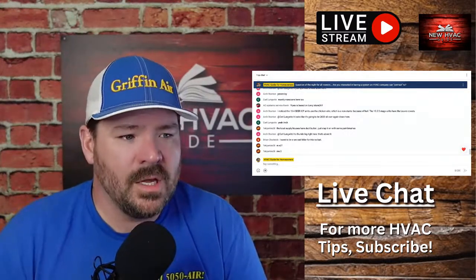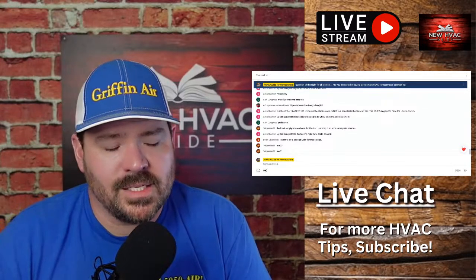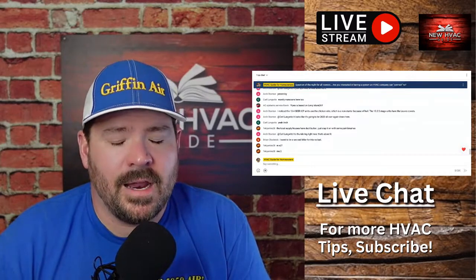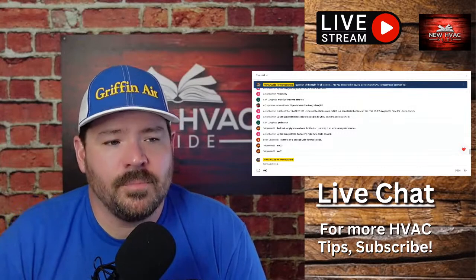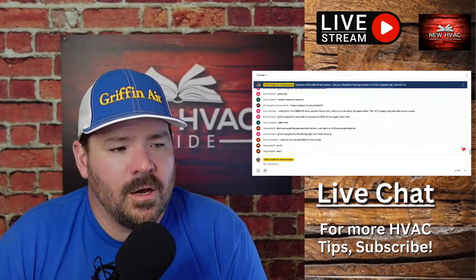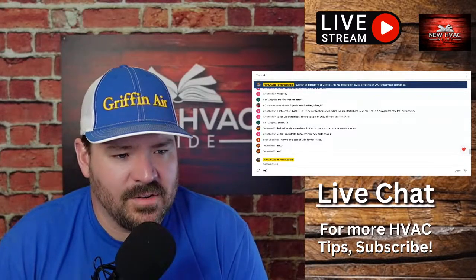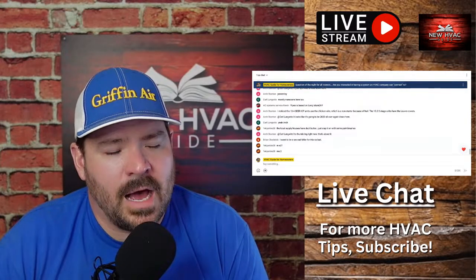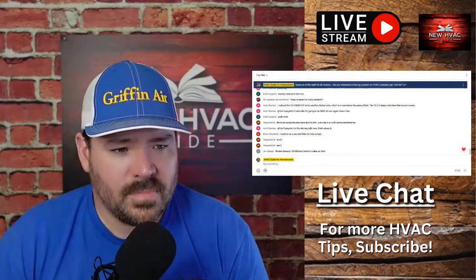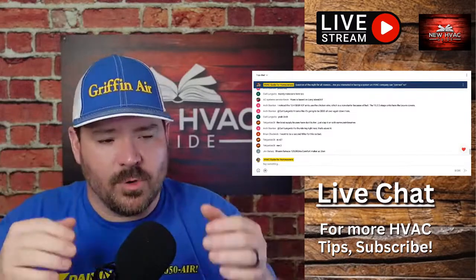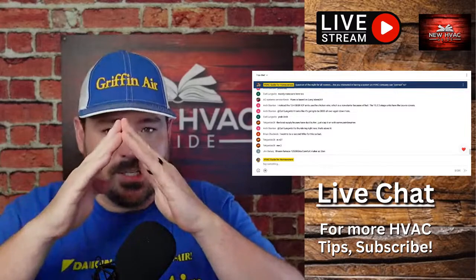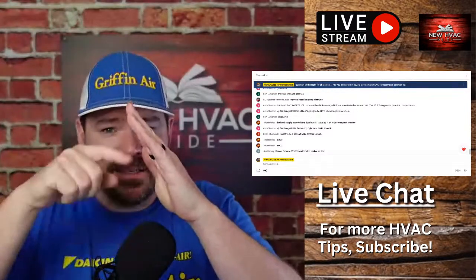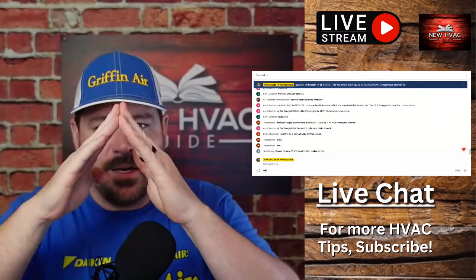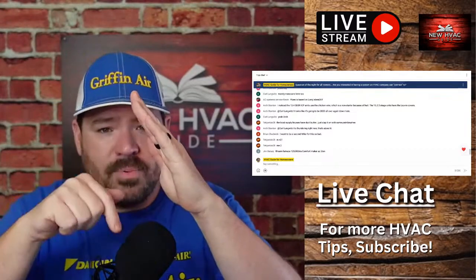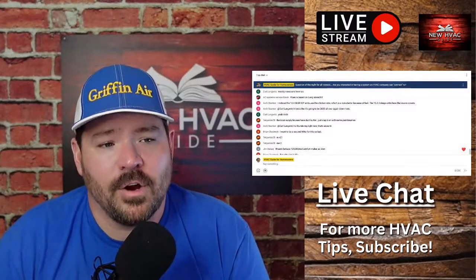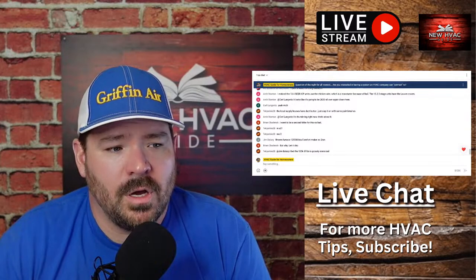Yes, there is. There's literally thermostats that you can turn on the extended fan runtime. The one I know off the top of my head that has it is the Honeywell 8000, because we've turned it on for dual fuel systems multiple times. But I'm sure it's not the only one, there's several out there with extended fan runtime. The other thing I would look at, Dave, is having your AC refrigerant checked. I don't know the configuration of your system, but I've seen A coils that will literally drip past the primary drain pan on the side. It's supposed to condensate and drain down into that pan, but it'll drip past it if the refrigerant is low or if there's an issue with the airflow. I would have that checked as well.